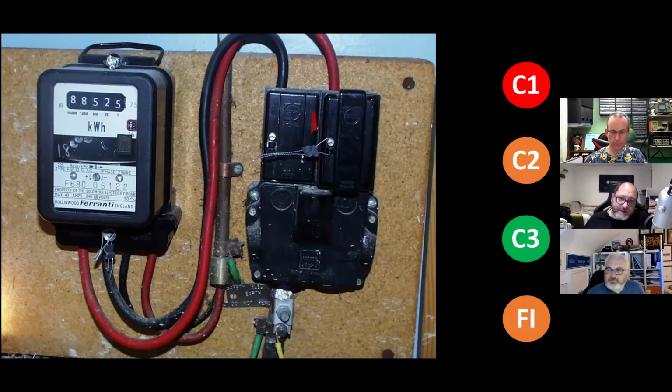We've gone 50% C2, 31% have gone C3, and 16% have gone FI. Yeah, I think that's pretty fair. I'm on a C3, C2, but then when I hear about the accessibility to the public and that pot, and it is fragile, as Paul said, a couple of whacks on that pushed me over to C2.